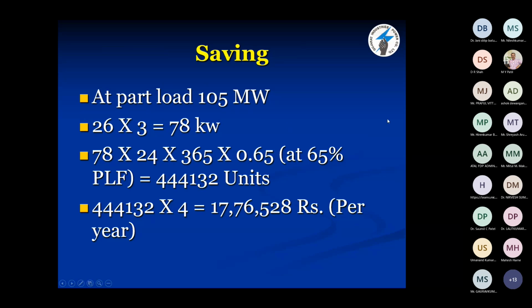Now this is the saving. At part load at 105 megawatt, 26 kilowatt per pump saving, into 3 pumps running, so 78 kilowatt is the saving. 78 kilowatt into 24 hours into 365 days, considering 0.65 utilization, then also 4,44,000 units is the saving. And in terms of money, it comes to 17,76,528 rupees per year.